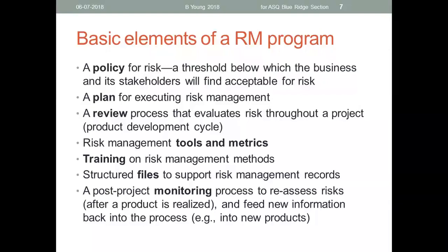When you are executing your risk management, you're going to have to document what you're doing, and all those documents need to be filed. A risk management program will have a risk management file to show all the activities that have occurred, and so that those records are accessible and maintainable, you will want to be thinking about how that file is structured.